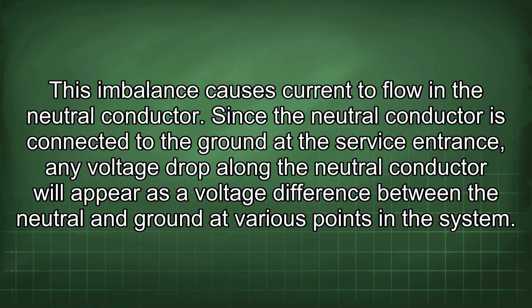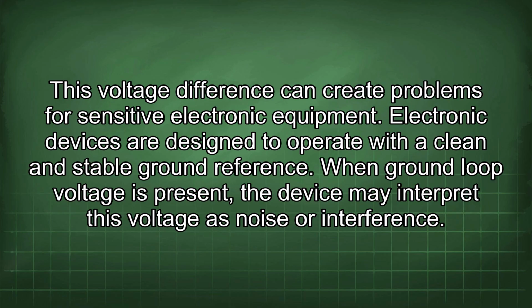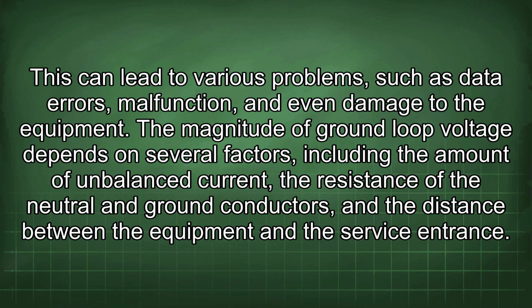Since the neutral conductor is connected to the ground at the service entrance, any voltage drop along the neutral conductor will appear as a voltage difference between the neutral and ground at various points in the system. This voltage difference can create problems for sensitive electronic equipment. Electronic devices are designed to operate with a clean and stable ground reference. When ground loop voltage is present, the device may interpret this voltage as noise or interference. This can lead to various problems such as data errors, malfunction, and even damage to the equipment.